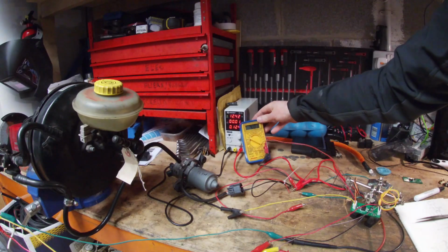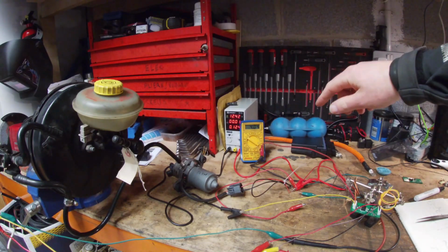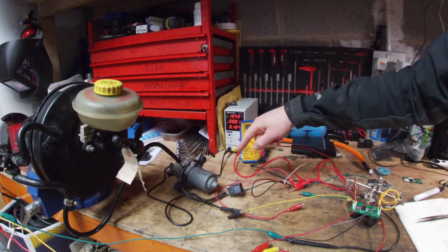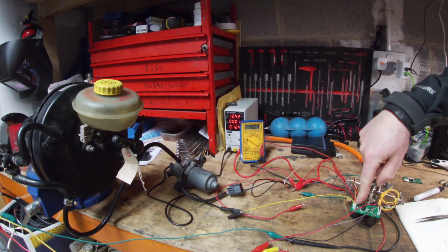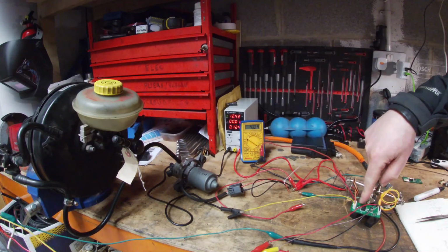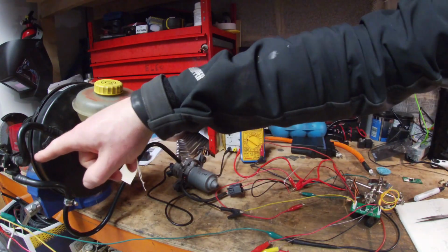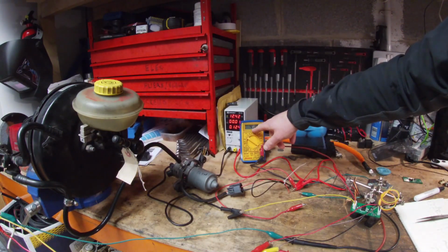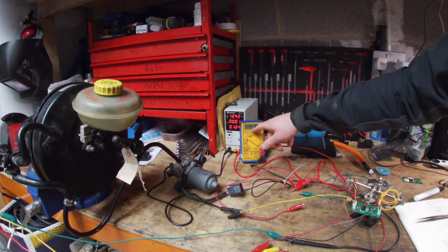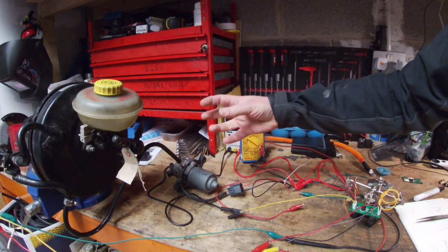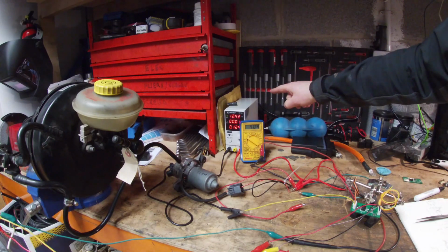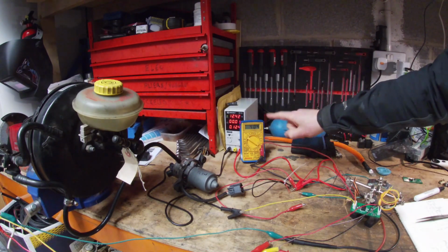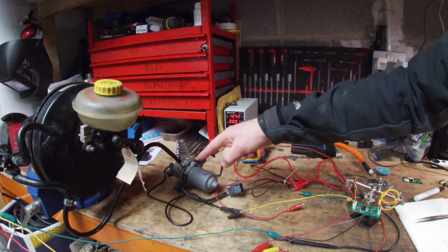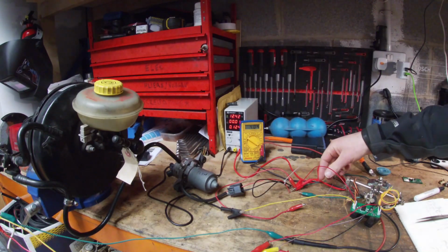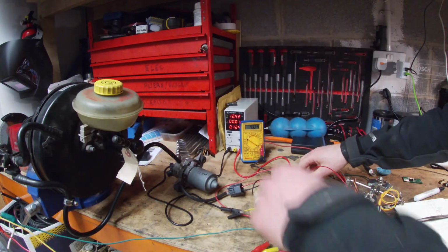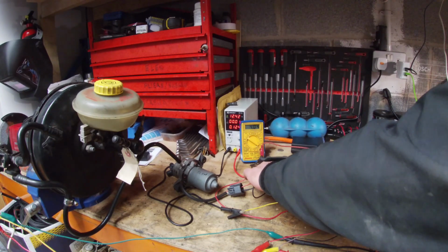So at the moment you can see that's at 4 volts. Basically what's happening is this is being fed 12 volts into the switch here. On the far side, it's feeding the switch 5 volts and returning 4.4. When that gets down to 0.7, that's when it knocks that off - that's when the vacuum is purged of all the air. So that's what we're going to do - you're going to see that dive as the vacuum takes shape. Takes shape? Takes no shape - the vacuum. So let's go for it.